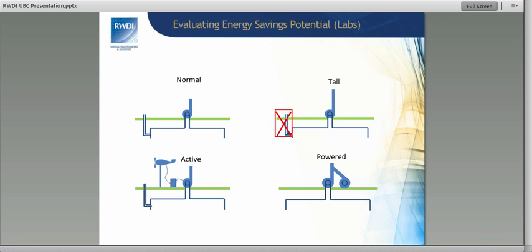Another way we can do it is we can use that wind analysis. We can look at probability. Let's say we've determined that there is a potential for contamination but it's only for a certain section of winds that happen, I don't know, 20% of the time. Well, we can set up an active system on the roof with an anemometer, which is something that measures wind speed and direction, to basically tell us, or tell an operator, when those good winds and when those bad winds are happening. When the bad winds happen, we turn it up, we get that velocity. When good winds are happening, when there's less chance of contamination, we can turn it down and save energy. The challenge there is that it's expensive and it's complicated.